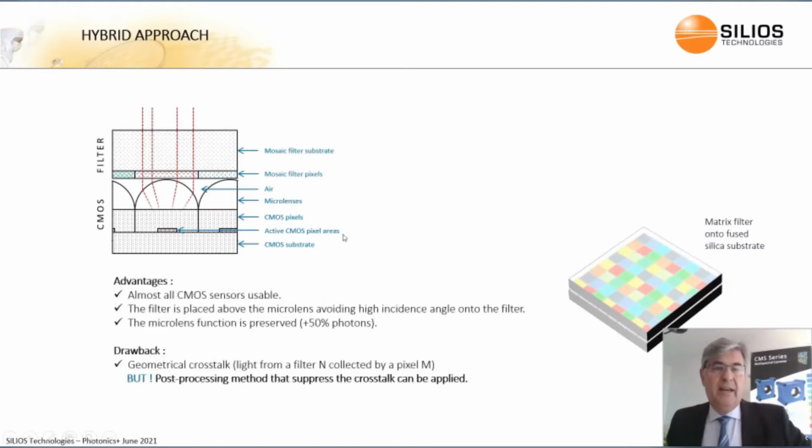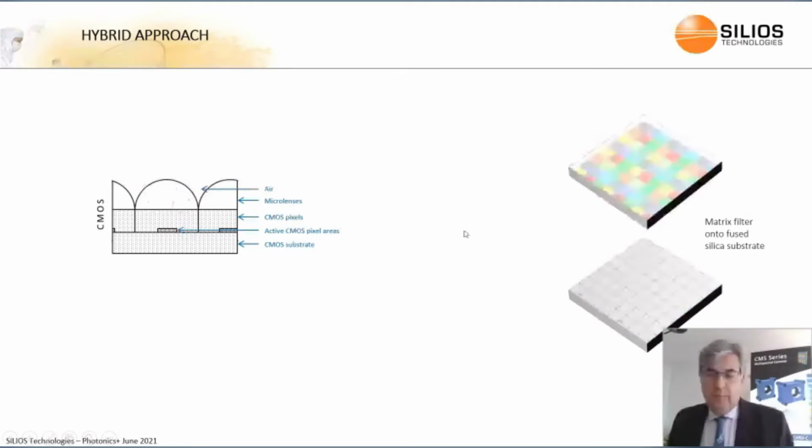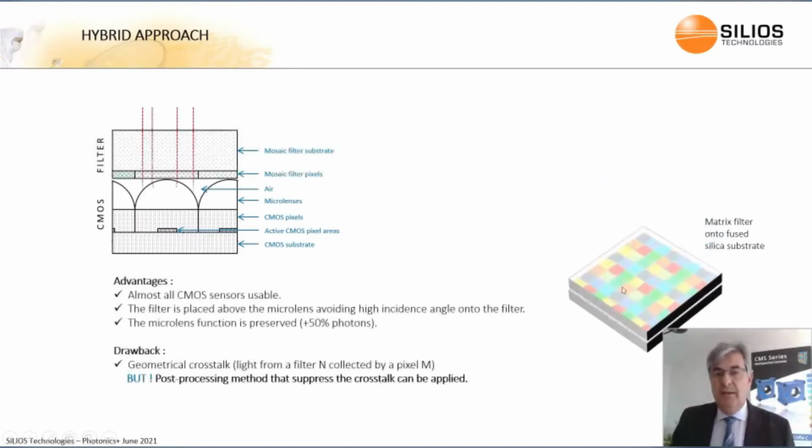The way our multispectral sensors are made is that we apply our multispectral filter and we align it pixel filter down exactly on the CMOS pixel. In the case of CMOS, because it can also work on a bundle of diodes, whatever the sensor. One important thing: we have developed some alignment benches to do the hybrid approach. So we work on the packaged sensor. We don't work at the wafer level. And this has several reasons.